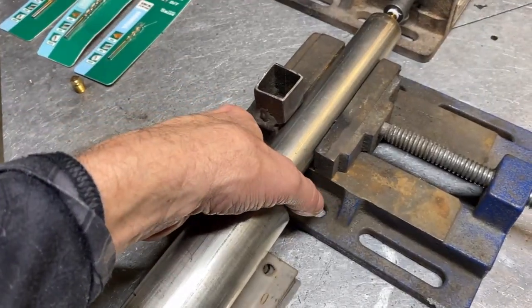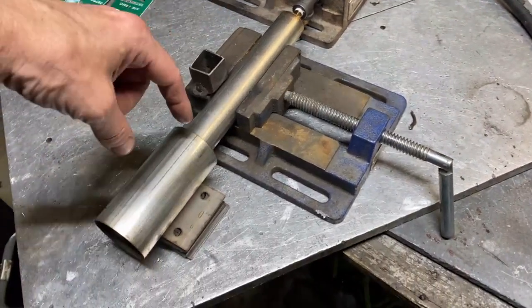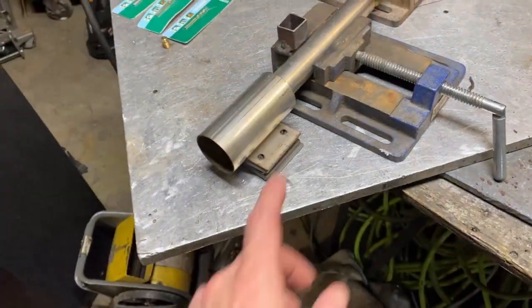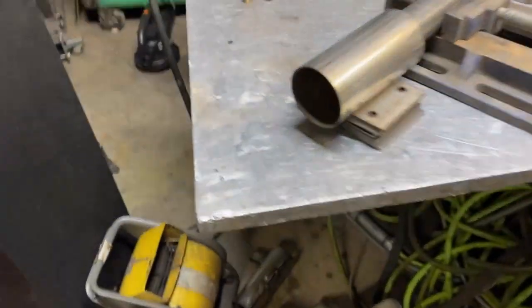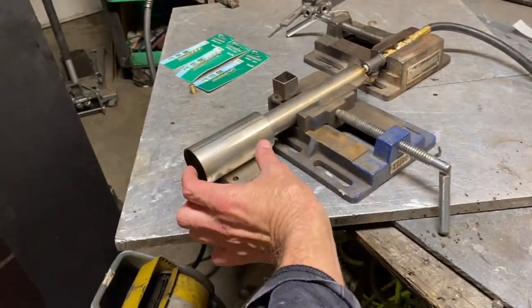Same thing right here with this secondary shroud — we have a dual Venturi going on here. This is also pulling a very strong vacuum, and without this on here the burner will not burn. I've been sliding this back and forth to determine what is the optimum size of this outer shroud.